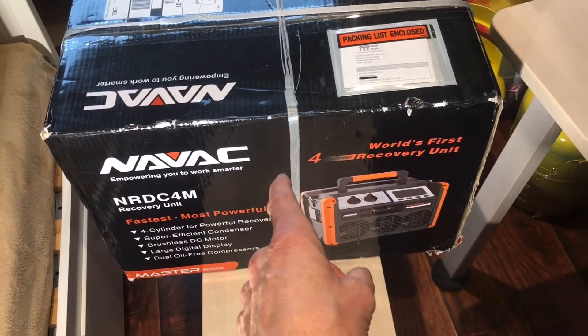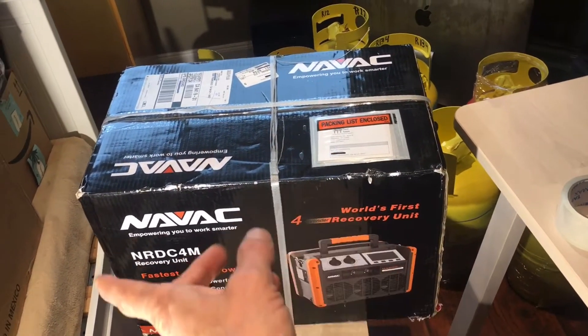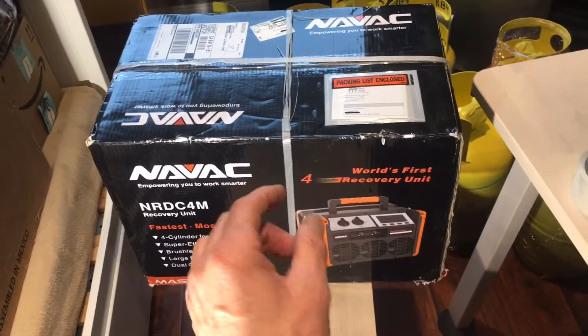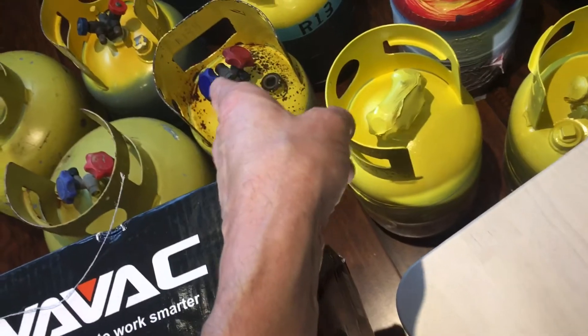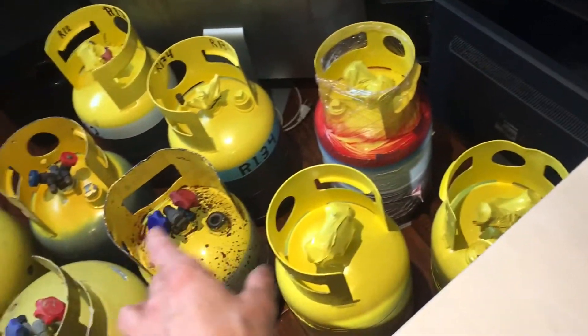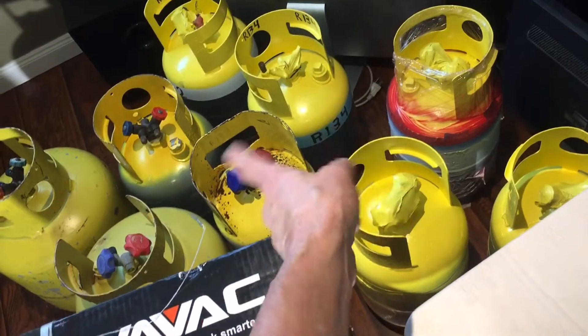The Fieldpiece was good for vapor recovery; one of my previous units was better for recovering liquid. For those in automotive who don't know the difference: R410A is a high-pressure gas, very different from R134a or R22. I also have R1234yf here — that's the new refrigerant. Automotive guys may not know the extreme differences in pressures and temperature relationships across refrigerants — I'll do a future video on that.